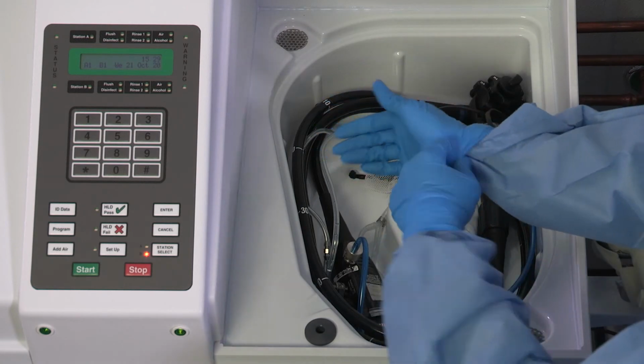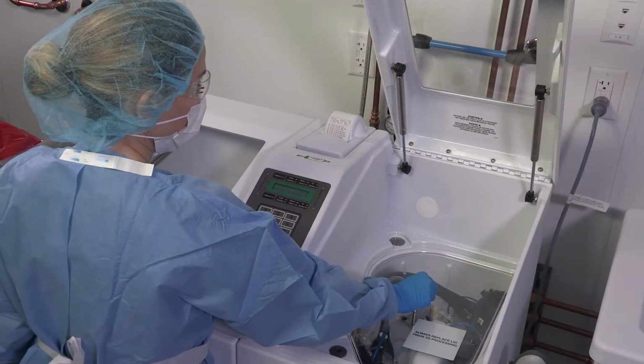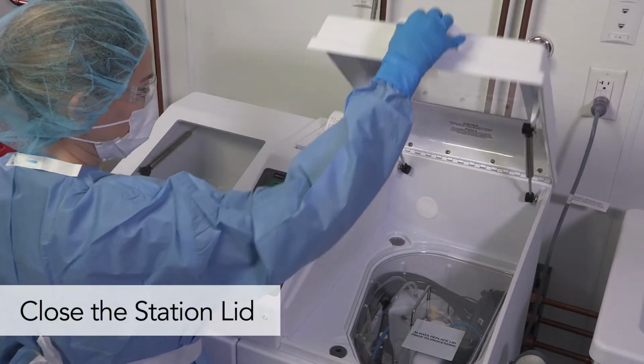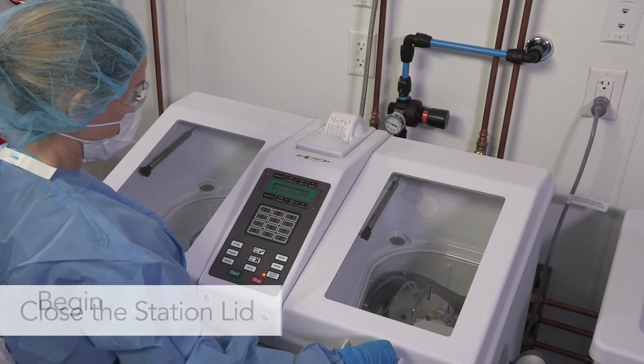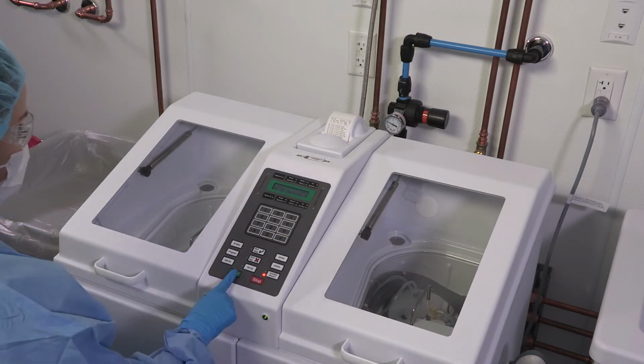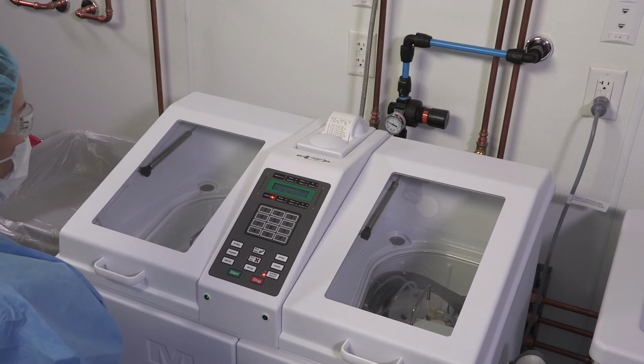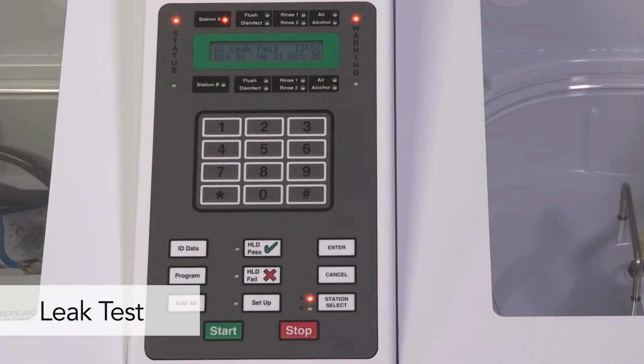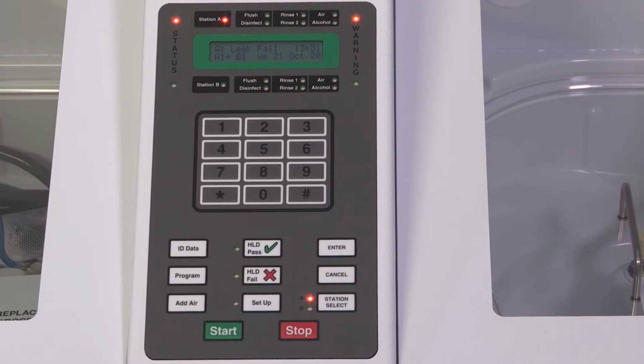Remove contaminated PPE. Finally, close the station lid. Press the Start button to begin the reprocessing cycle. The first operation is checking for air leakage. The endoscope is pressurized and monitored for 40 seconds.